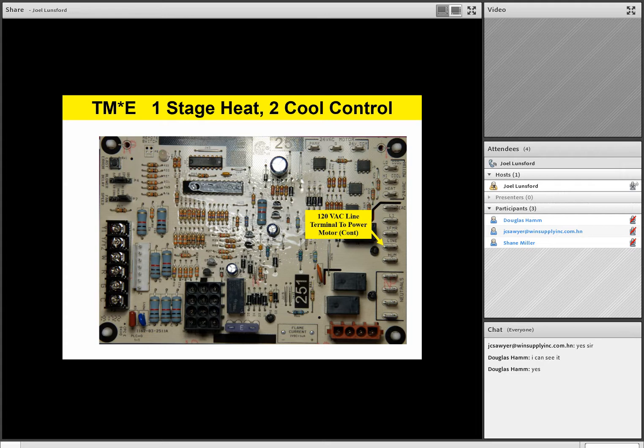All right, below that line terminal we have a 120 volt humidifier output. On this control board, we give you the capability of controlling the humidifier, energizing the humidifier from this 120 volt AC humidifier terminal. It should be noted this is a dry isolated relay output, and it gives us the capability of running a humidifier off of our control board without actually having to have a bunch of extra relays or extra controls. So that's pretty nice. This humidifier terminal will be energized anytime we have a W or a heating call.